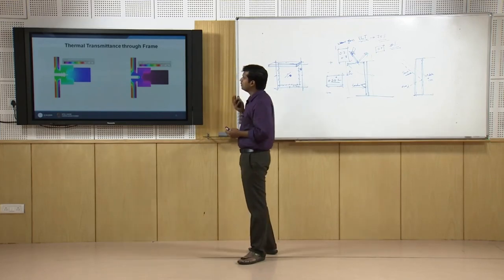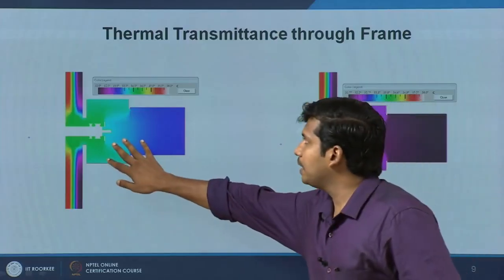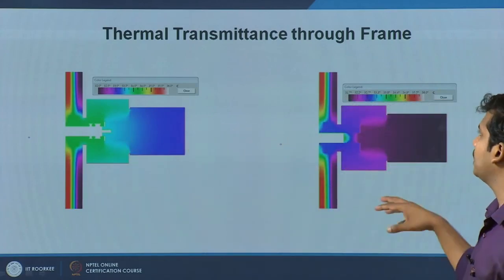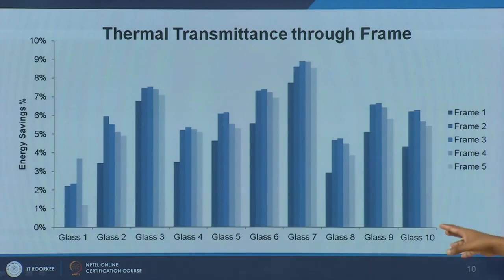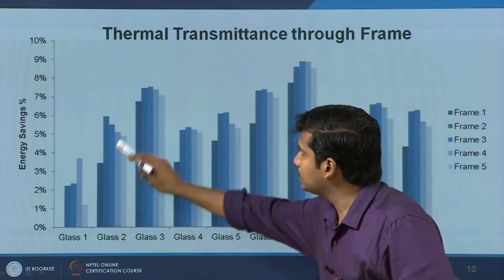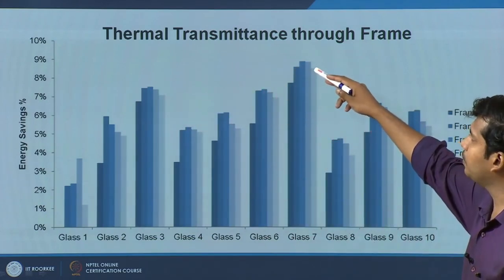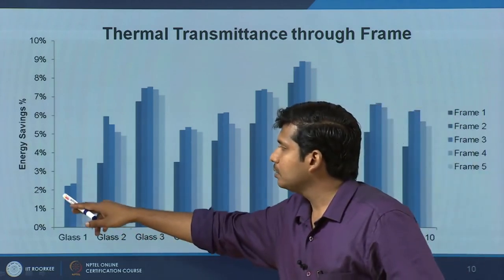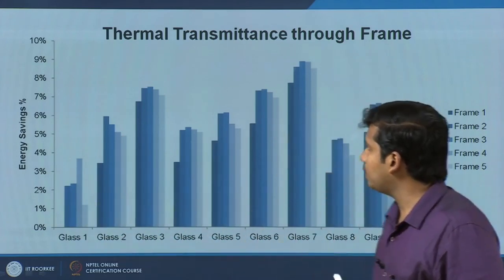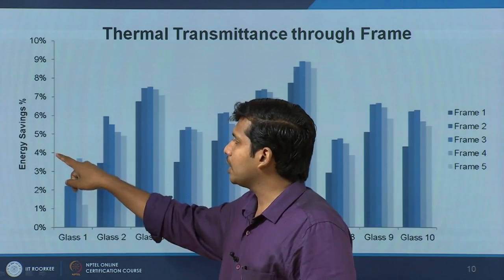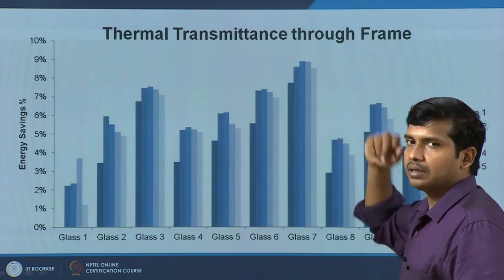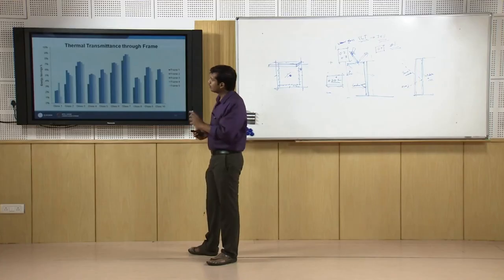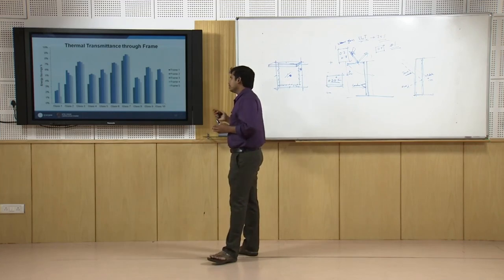To give a better picture, two different frame systems were compared. Heat transfer through one frame is relatively higher than the other. Looking at 10 different glasses and 5 different frames, the amount of energy saving varied significantly. With an efficient glass you get about 8 to 9 percent saving, whereas with a less efficient glass you get around 1 to 2 percent saving. Even with a less efficient glass, choosing an efficient frame can get you up to 4 percent energy saving. Conversely, even with good glass, a poor frame can cost you 1.5 to 2 percent of estimated energy savings. The frame has a crucial role in overall system energy efficiency.